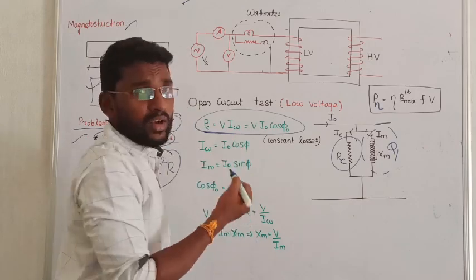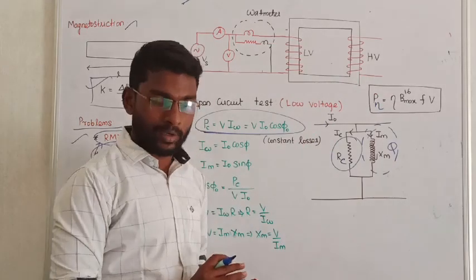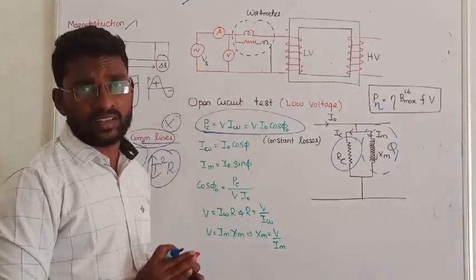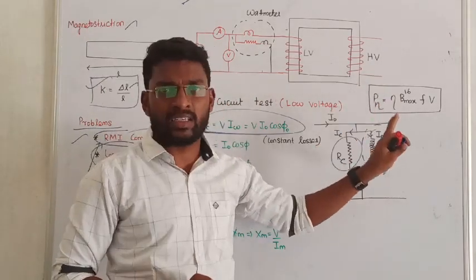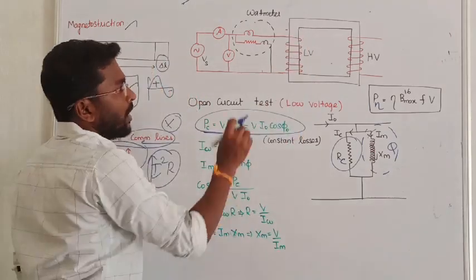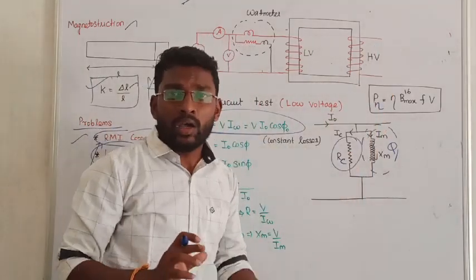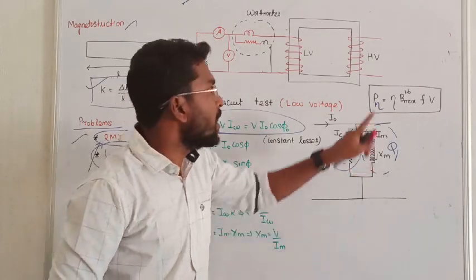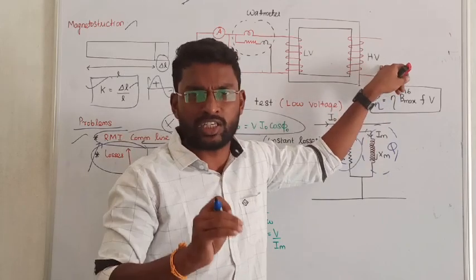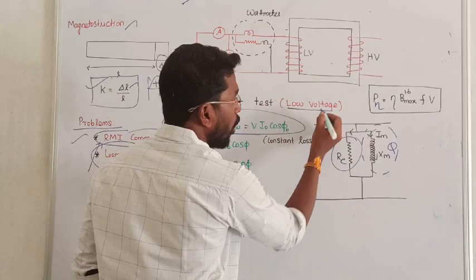The second point about the open circuit test is which side it is connected on. Usually in our transformer we have two sides: one is the HV winding side and one is the LV winding side. The open circuit test is conducted on the low voltage side. If you apply voltage on the high voltage side, it may lead to insulation damage. So to avoid high voltage stress, the open circuit test is always conducted on the low voltage side.